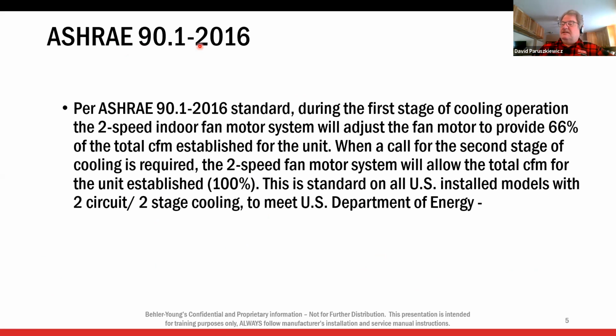ASHRAE 90.1-2016. Just to summarize what this is, back in 2016, when this standard came along, this is an efficiency standard on our blowers. Commercial rooftop units used to all be single speed blowers. Well, since 2016, anything 5 ton and larger under this standard has to have a 2-speed blower.